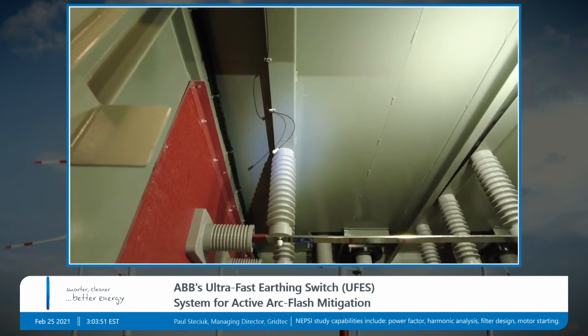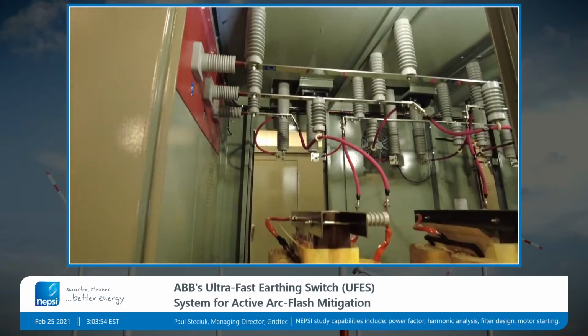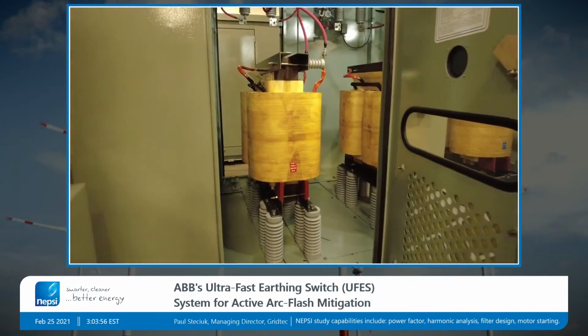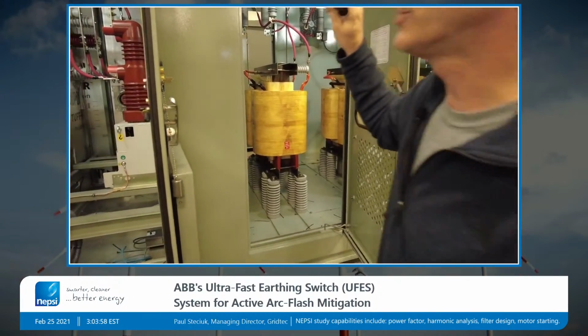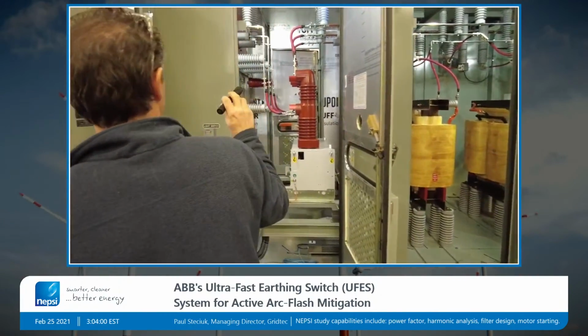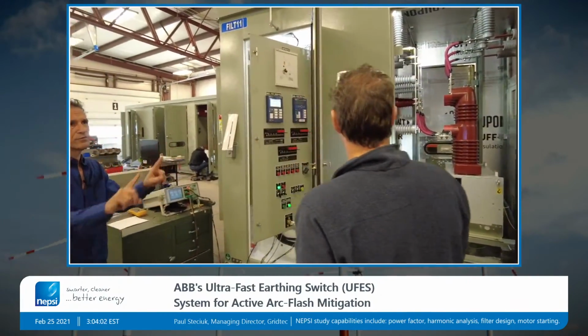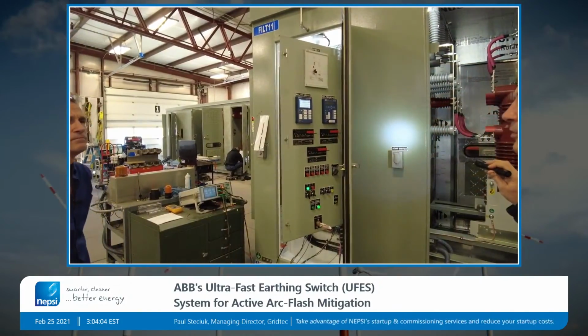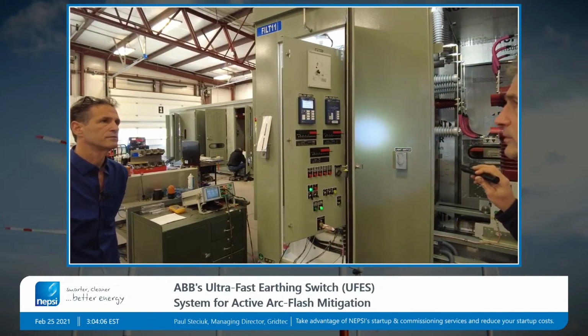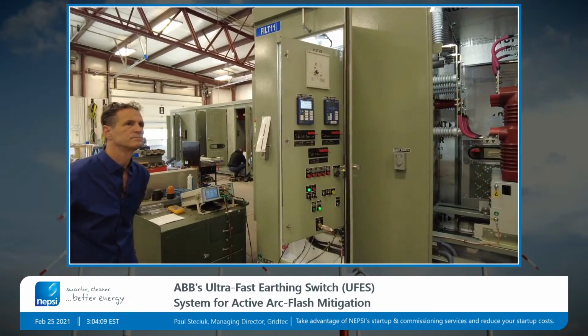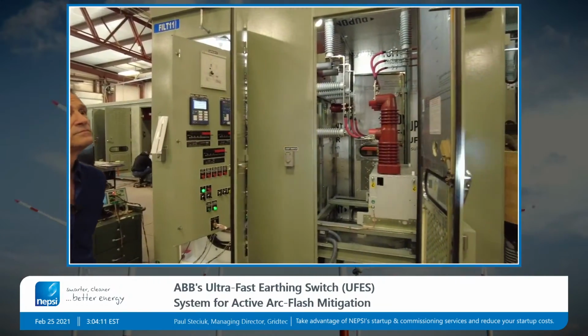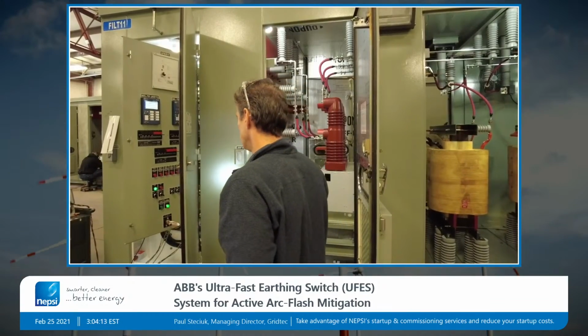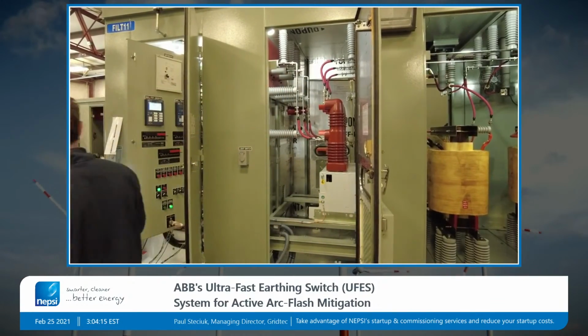And these optical sensors are kind of like an eye, so they look in all directions, in the direction that they're facing. So, Pete, do you do an overlap on the sensors? So it's an overlap. Yeah, we always do 2, so they're overlapping one another. Okay. And then we expect quite a bit of reflection inside during an arc. I think during an arc period, it's going to be pretty bright in there.